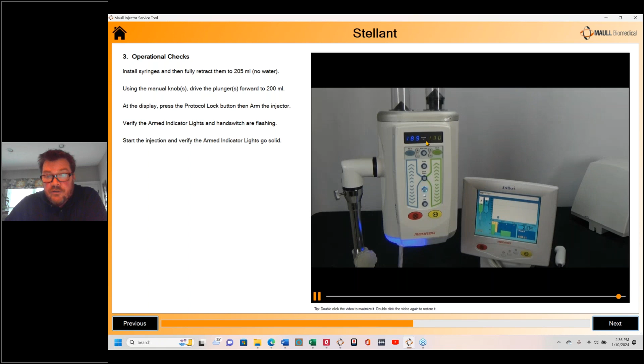And then once the injection is complete, the one we just did, we want to make sure that we have very specific volumes left in each one. And then we document the results over here. We want to make sure that syringe A, if this was a dual head injector, meaning there were two syringes, which most of them are, after this injection was over, syringe A had 30 milliliters left and syringe B had 170 milliliters left, plus or minus 1 milliliter. Or if it was a single head, meaning just one syringe, a contrast syringe, make sure that the syringe has 0, plus or minus 1 milliliter. It's a different shot. So just general operation inspection, we will say it passed.